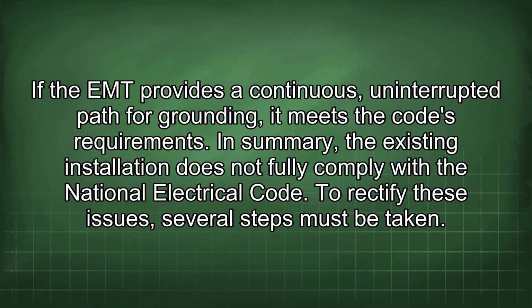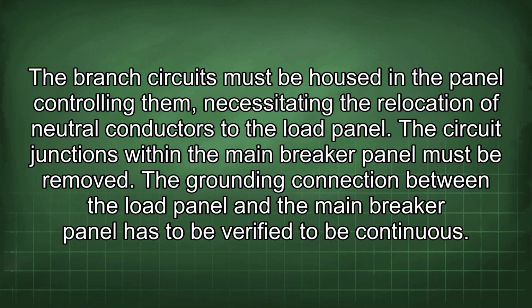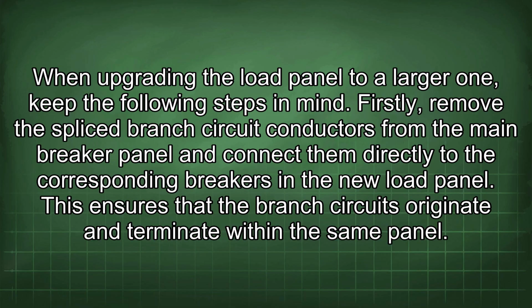To rectify these issues, several steps must be taken. The branch circuits must be housed in the panel controlling them, necessitating the relocation of neutral conductors to the load panel. The circuit junctions within the main breaker panel must be removed. The grounding connection between the load panel and the main breaker panel has to be verified to be continuous. When upgrading the load panel to a larger one, keep the following steps in mind. Firstly, remove the spliced branch circuit conductors from the main breaker panel and connect them directly to the corresponding breakers in the new load panel. This ensures that the branch circuits originate and terminate within the same panel.